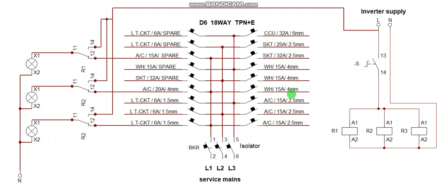If you also need a particular AC to be fed by inverter, or you want inverter to feed any of the power circuit, interface with a relay, look for a relay contact and put it there. Then these are the coil of the relay. So this is my inverter supply. You take the supply of the inverter, go to the relays and feed them on parallel, on parallel method, feed them up.